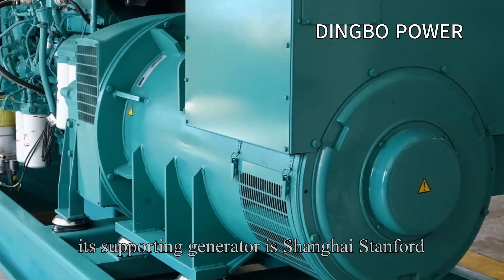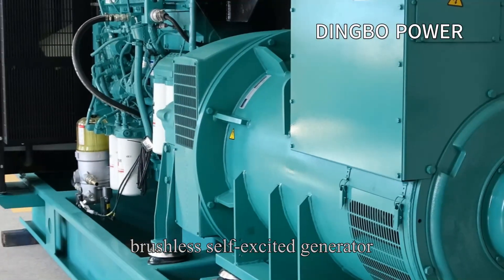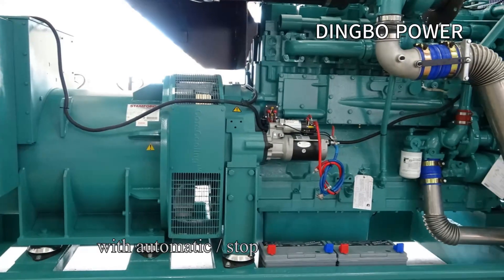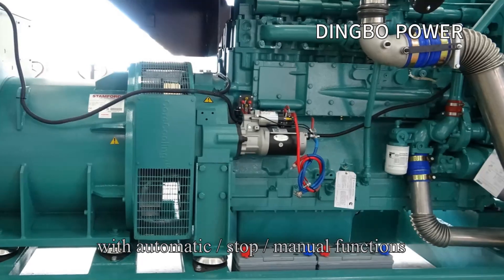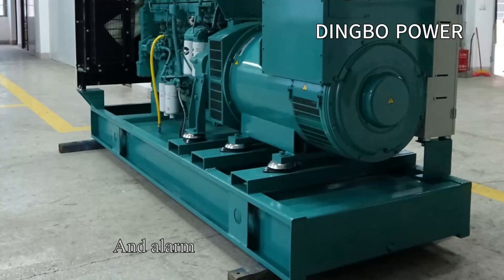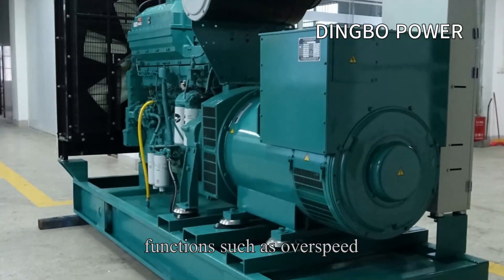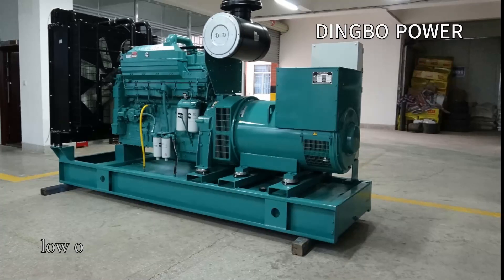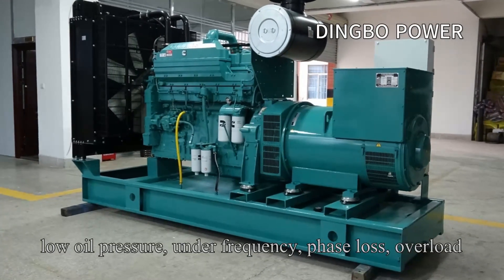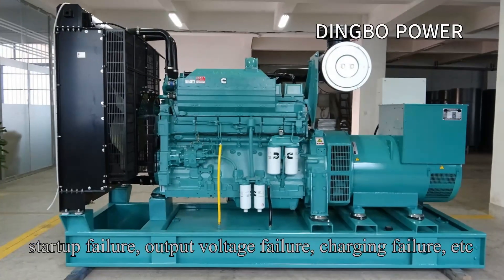The supporting generator is a Shanghai Stamford Brushless Self-Excited Generator, which adopts a Jihongji technology control panel with automatic, stop, and manual functions, start delay and shutdown delay functions, and alarm and shutdown protection functions such as overspeed, high water temperature, low oil pressure, under-frequency, phase loss, overload, start-up failure, output voltage failure, and charging failure.